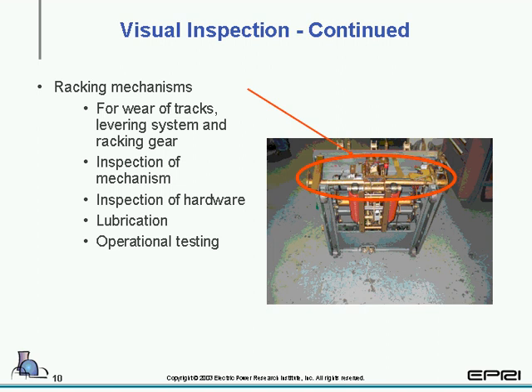The next one we'll take a look at, you should be looking at on your screen, is the racking mechanism. We also have a list of items, as well as when you're looking in the cubicle, you may see filings of some type on the edges where the racking mechanism would ride. And if you have any challenges with the breaker racking in or racking out binding, you're also going to want to take a little extra time inspecting the racking mechanism to see if there's any warping or damage.